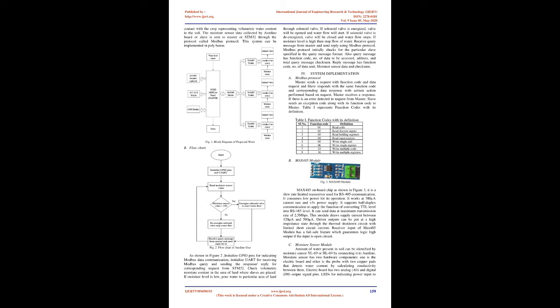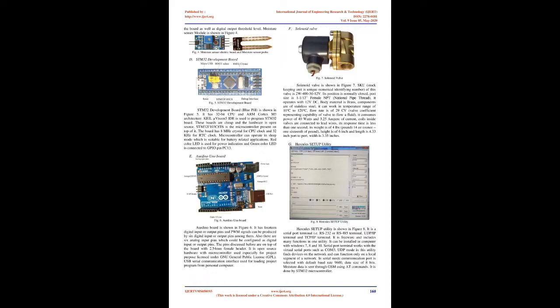Modbus protocol initially checks for the particular slave specified in the query message format. The query message includes a function code, number of data to be accessed, address, and total query message checksum. The reply message includes a function code, number of data sent, moisture sensor data, and checksum. The master sends a request with a function code and data request, and the slave responds with the same function code and corresponding data response with a certain action performed. If an error is detected in the request from the master, the slave sends an exception code along with its function code. Table I represents function codes with their definitions.